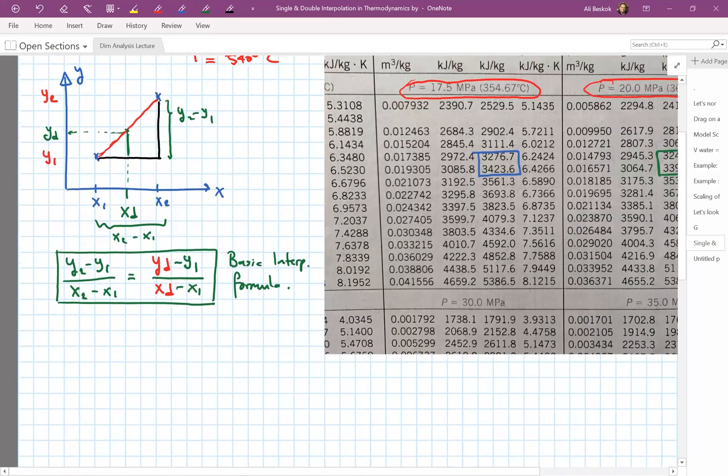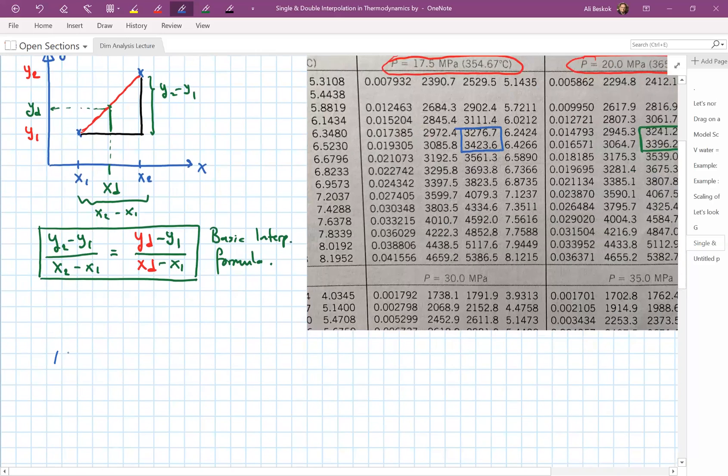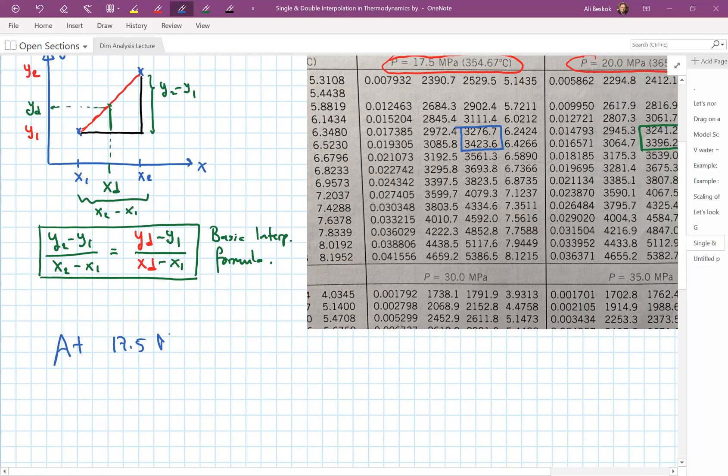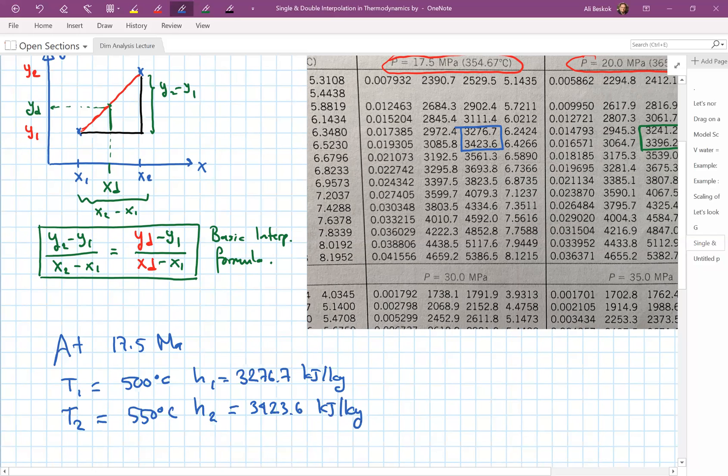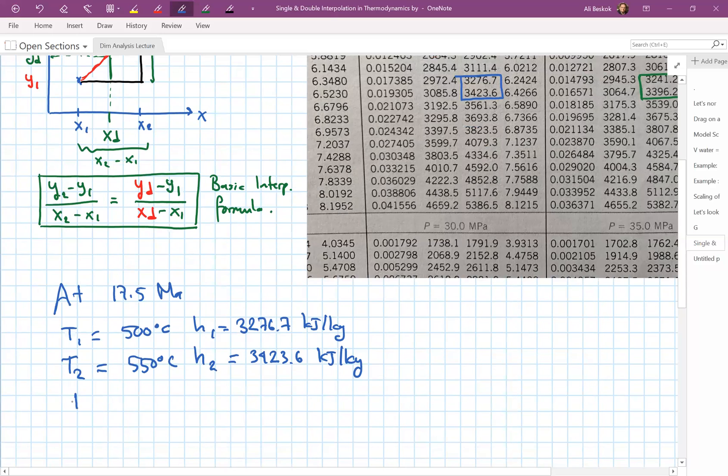Let's start doing that. First, the blue box at 17.5 MPa. At 17.5 MPa, T1 is 500 degrees Celsius, T2 is 550 degrees Celsius. H1 is 3276.7 kilojoules per kilogram, while H2 is 3423.6 kilojoules per kilogram. I have these two values, and I'd like to figure out the enthalpy value at the desired temperature of 540 degrees Celsius.